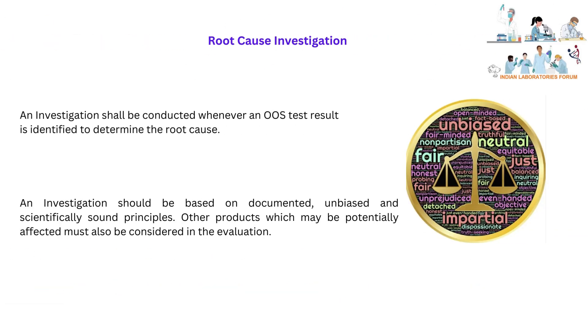An investigation shall be conducted whenever an OOS test result is identified to determine the root cause. An investigation should be conducted using unbiased and scientifically sound principles. Other products that may be potentially affected must also be considered. Investigation should be done by a technically competent and independent person, and impact assessment should be done to identify the potential effect on other products.